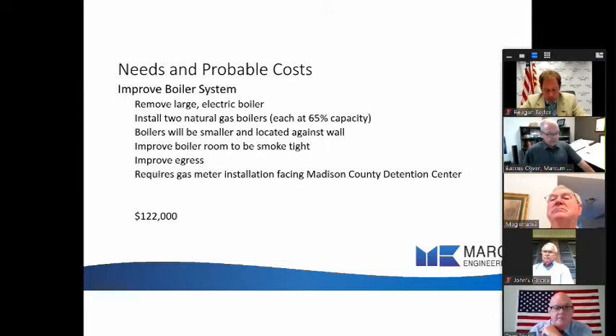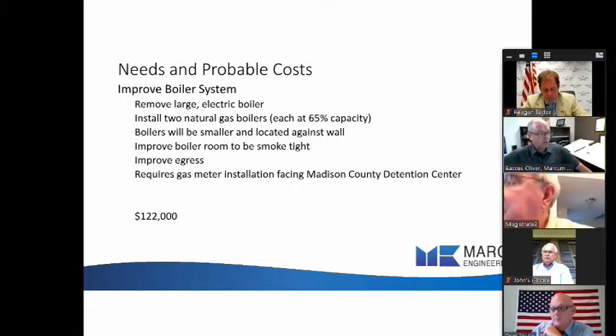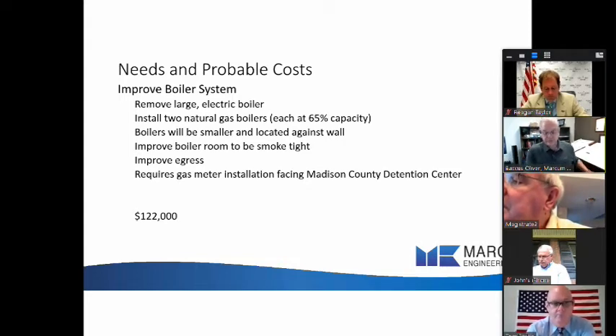Boiler system. I recommend removing the large electric boiler and installing two natural gas boilers, each of them sized at 65% of the needed load. The reason for this is if we lose one boiler, the second one could basically get us by in mild weather, and it can get us by in an emergency situation. While it's not a full 100%, engineers generally size them at 65% so that we're getting by. But I would have a primary boiler, a second boiler that comes on the coldest of days, and then a second boiler that's standing there ready for failure of the first.